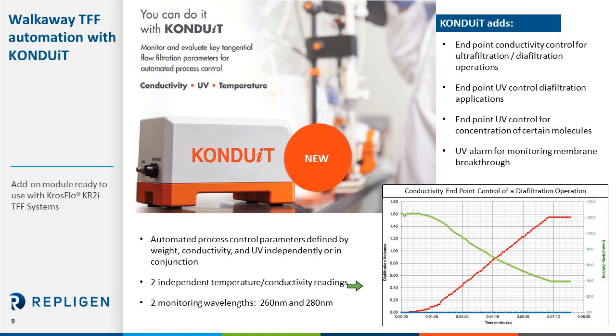We are now very excited to add the KONDUiT to our suite of system components. KONDUiT is an add-on module ready to use with new and previously installed KR2i systems. The KONDUiT supports real-time monitoring and endpoint control of solution conductivity, UV, and temperature for TFF operations. With the launch of KONDUiT, KF Comm is now capable of controlling your process via conductivity and UV, along with weight, either independently or in conjunction with one another. KONDUiT can support two independent temperature and conductivity readings, as well as two UV readings.